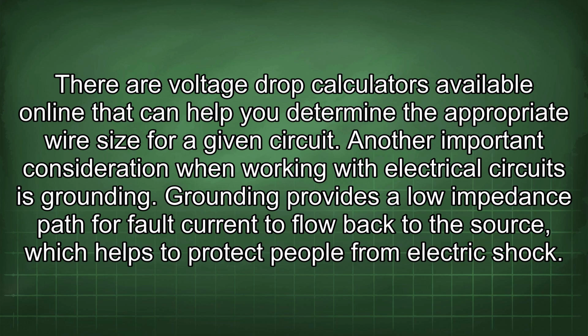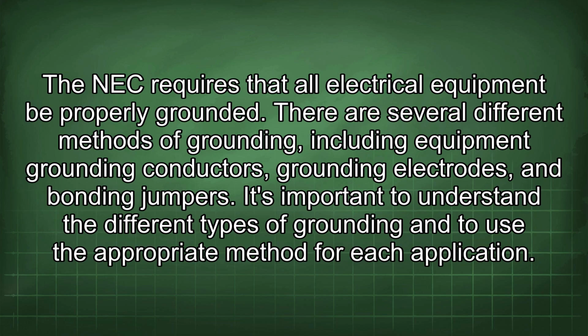Another important consideration when working with electrical circuits is grounding. Grounding provides a low impedance path for fault current to flow back to the source, which helps to protect people from electric shock. The NEC requires that all electrical equipment be properly grounded. There are several different methods of grounding, including equipment grounding conductors, grounding electrodes, and bonding jumpers. It's important to understand the different types of grounding and to use the appropriate method for each application.